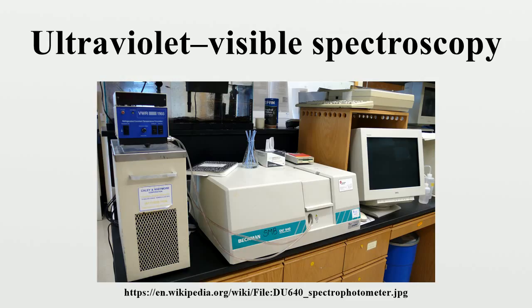Specialized instruments have also been made, including attaching spectrophotometers to telescopes to measure the spectra of astronomical features. UV-visible microspectrophotometers consist of a UV-visible microscope integrated with a UV-visible spectrophotometer. A complete spectrum of the absorption at all wavelengths of interest can often be produced directly by a more sophisticated spectrophotometer; in simpler instruments, the absorption is determined one wavelength at a time. Microspectrophotometry of microscopic samples is done by integrating an optical microscope with UV-visible optics, white light sources, a monochromator, and a sensitive detector such as a CCD or photomultiplier tube. As only a single optical path is available, these are single-beam instruments.